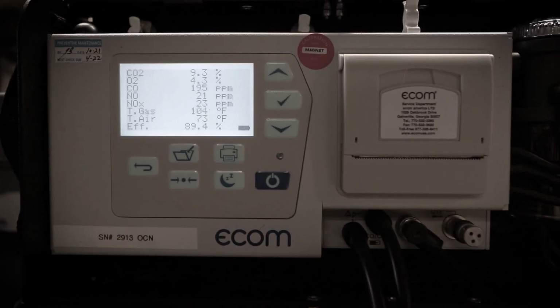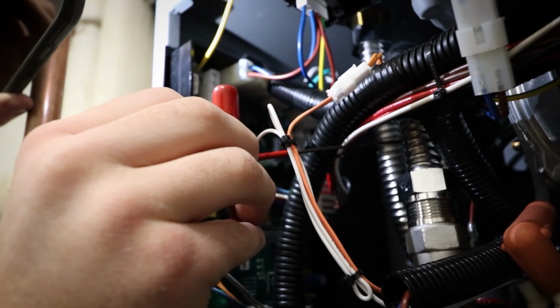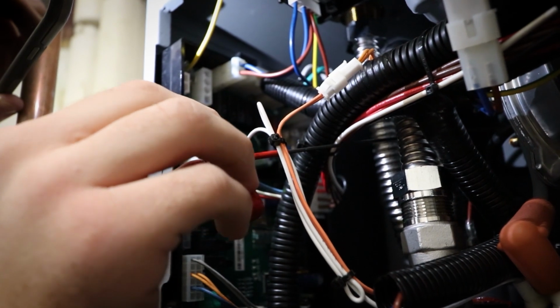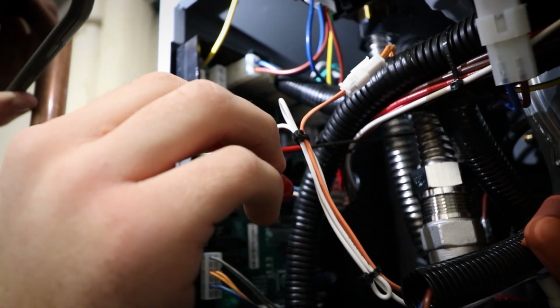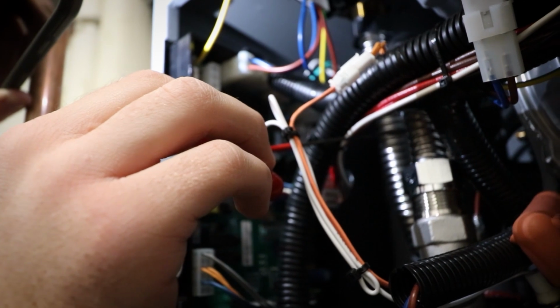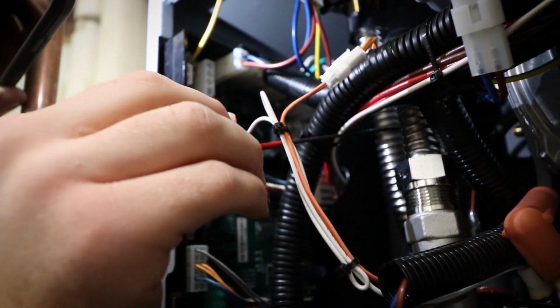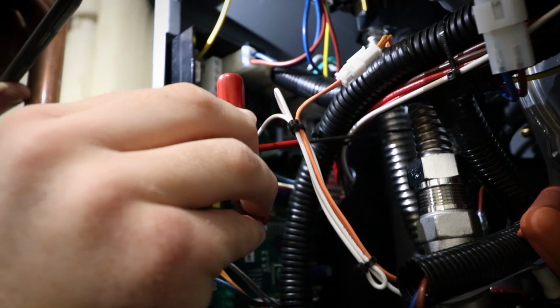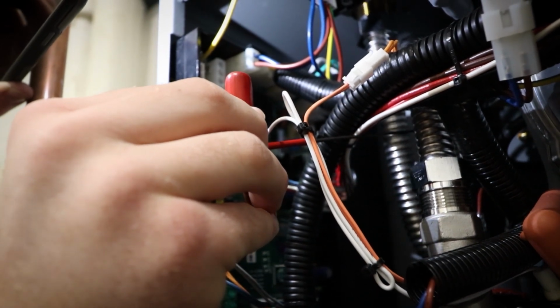For natural gas units, we want to set the CO2 on high fire between 9.1 and 9.3%. On propane units, the CO2 needs to be between 10.1 and 10.5%. Additionally, make sure the CO level is less than 200 parts per million. If an adjustment is needed, locate the high fire screw on the gas valve and turn it counterclockwise to increase the CO2 percentage and clockwise to decrease the CO2 percentage. Do not adjust more than 1/4 turn at a time.